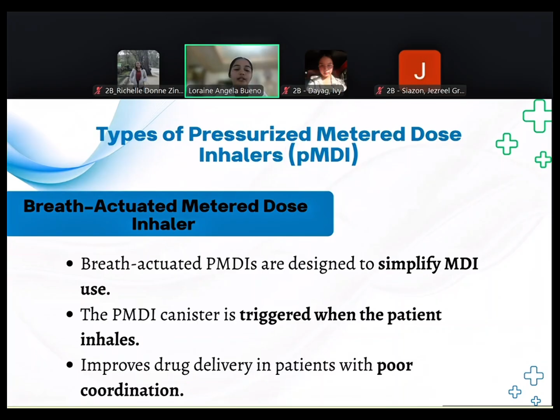On the breath-actuated pressurized metered dose mechanism, delivery is primed by raising the lever. Inhalation at 22 to 26 liters per minute triggers dose release. The device is reset by lowering the lever. So when the device is primed, it is ready to release the drug. When the patient breathes in at a flow of 22 to 26 liters per minute, the metered dose is released automatically. Then the device is reset for the next use.